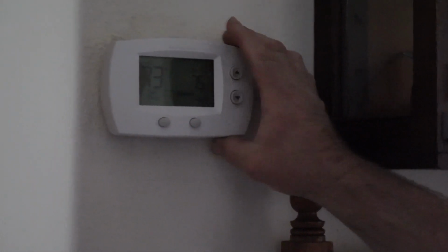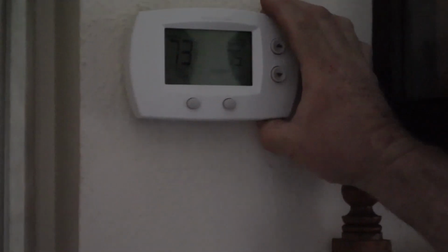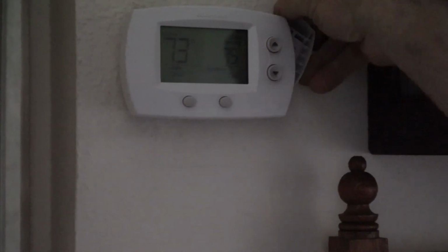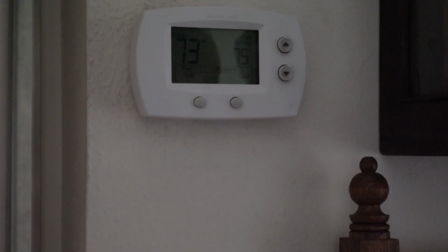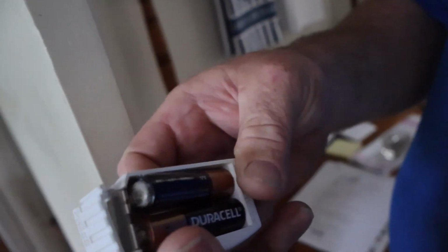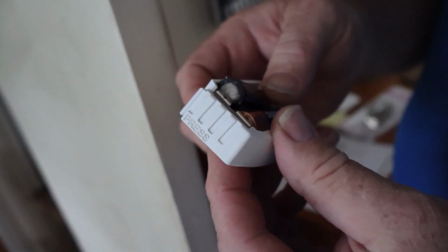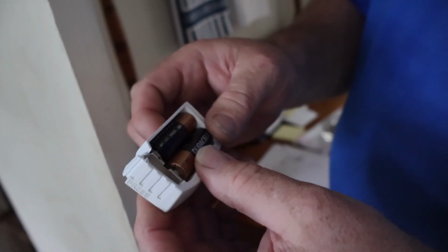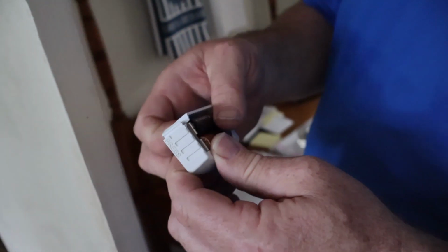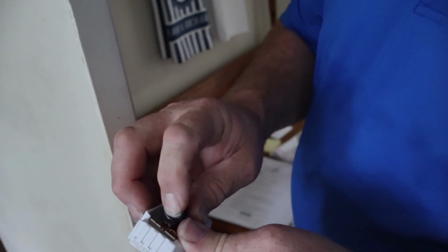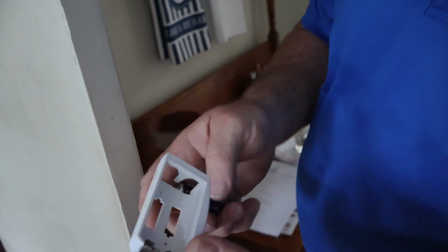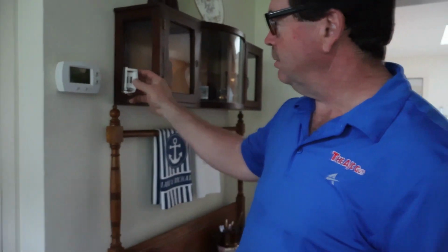The thermostat is something we like to check just to confirm that the batteries are good, or in some cases they're not even needed. So I'm going to take these batteries out and see what they look like. If you notice, the battery is corroded, and if that acid from the battery gets onto any electronics below or wherever, it can cause the thermostat to fail prematurely. I'm going to remove these batteries because I don't think we need them, because the 24 volts is controlling the thermostat.